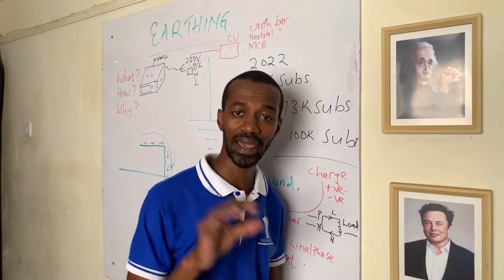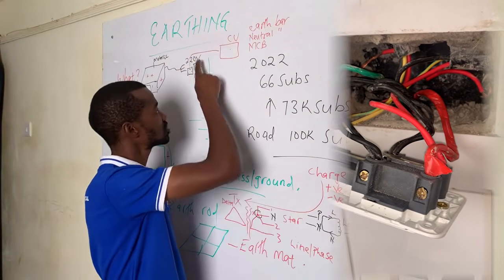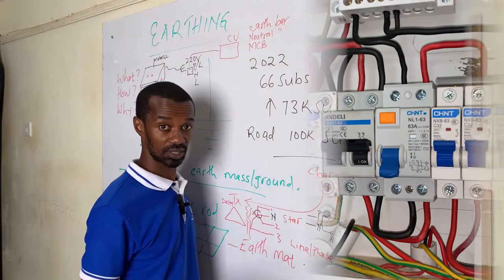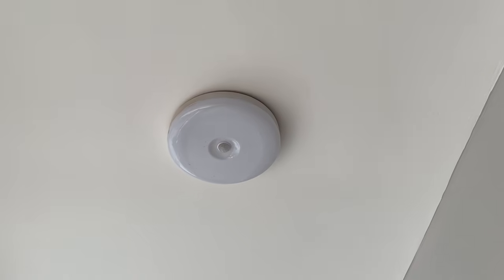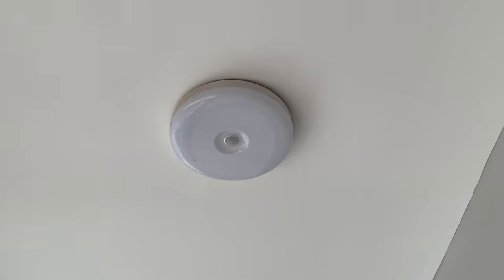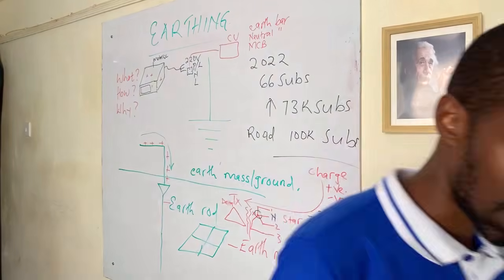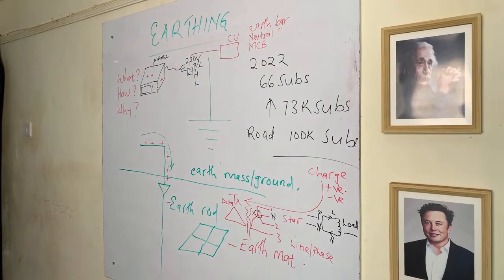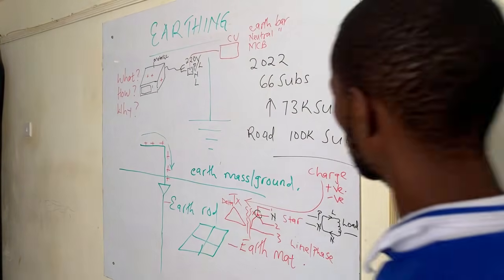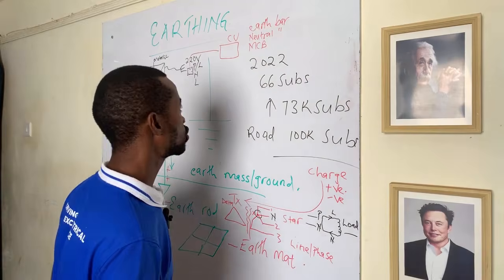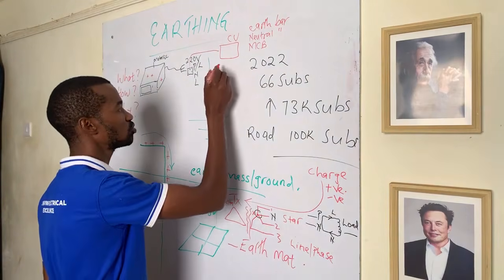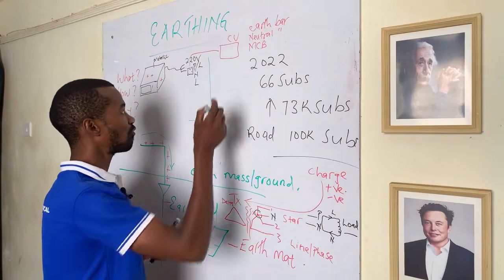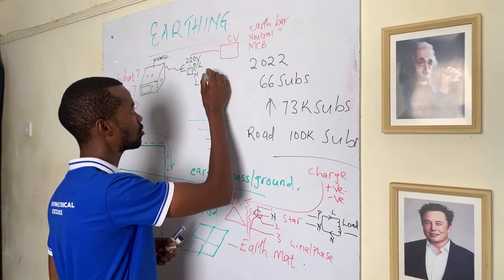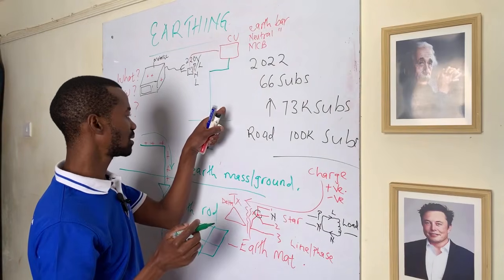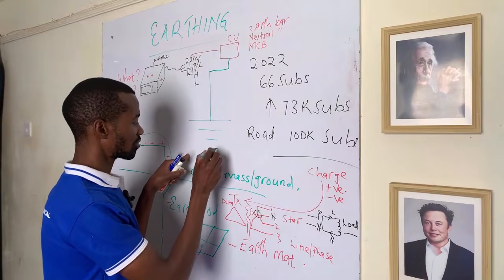This is where the wiring comes in handy. The wiring from the sockets and all the lighting points has to be in contact with the earth bar in the consumer unit, and that has to be checked properly. Apart from getting all the way to the consumer unit, we also need to be sure that from the consumer unit, the continuity of the earthing goes all the way to the meter board, and from the meter board to the earth rod.